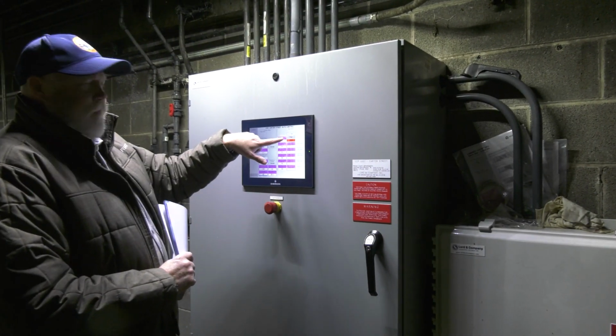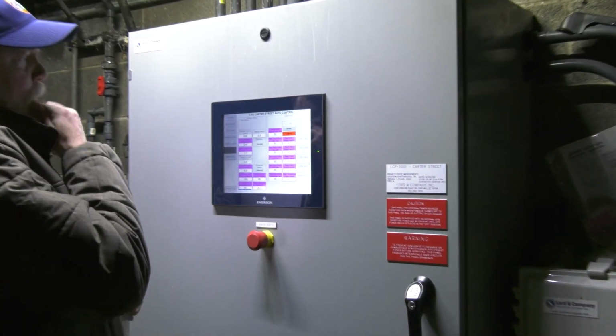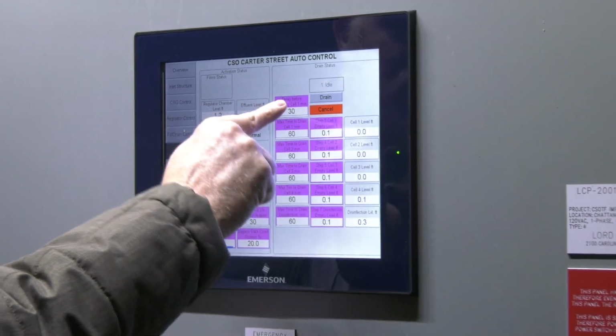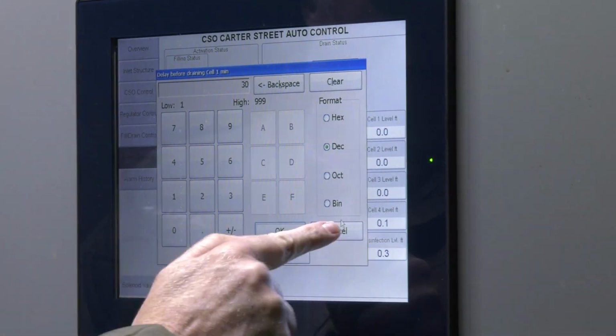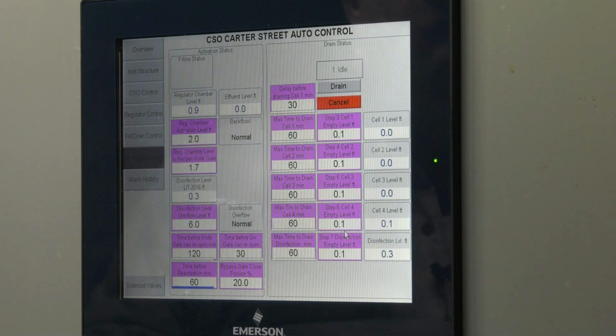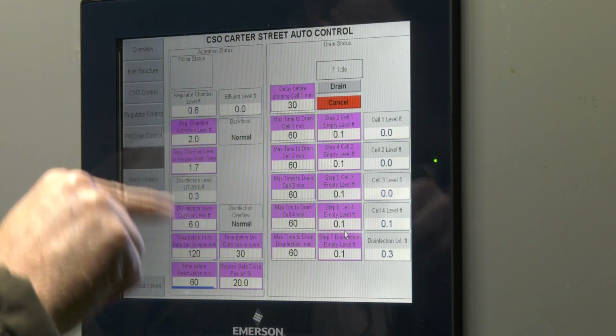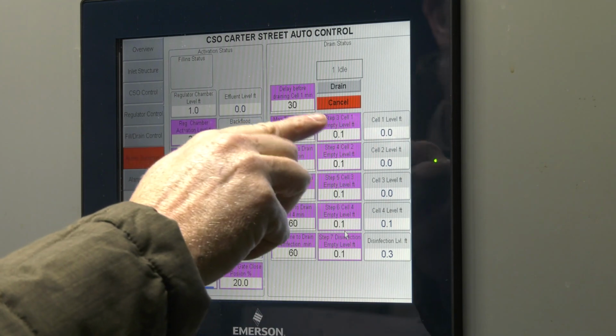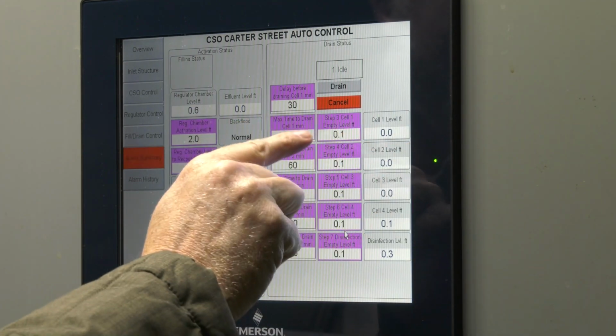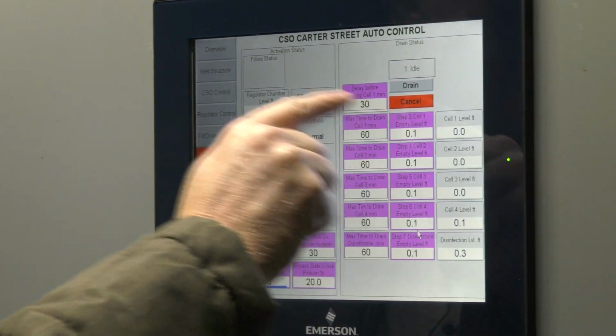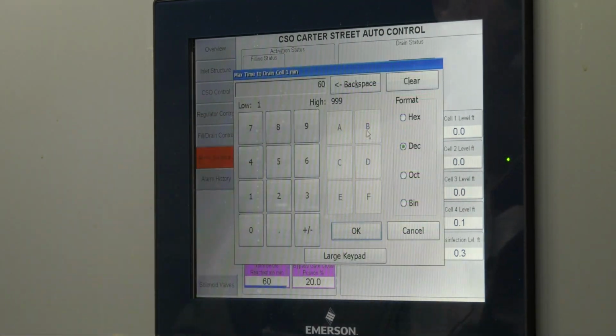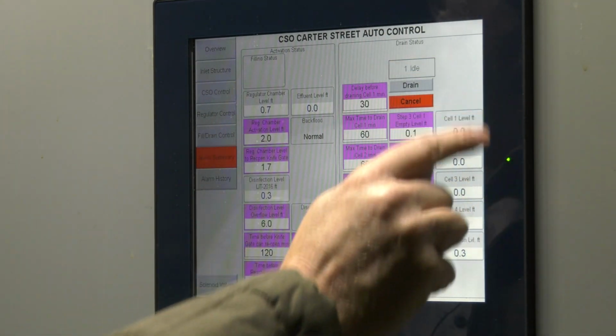All righty. The drain sequence initiates when you press the drain button, and then it'll wait an operator adjustable set point or time. Right now it's set for 30 minutes. After 30 minutes, it'll open each cell after the cell level is less than the operator adjustable set point, or it's been 60 minutes. Again, operator adjustable. It'll step through each cell.